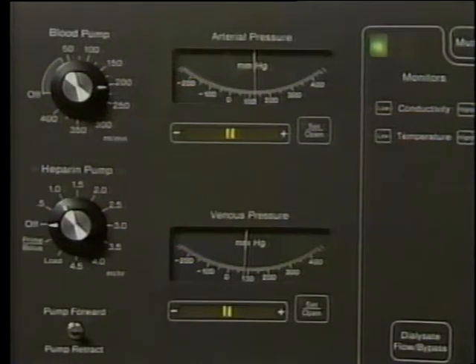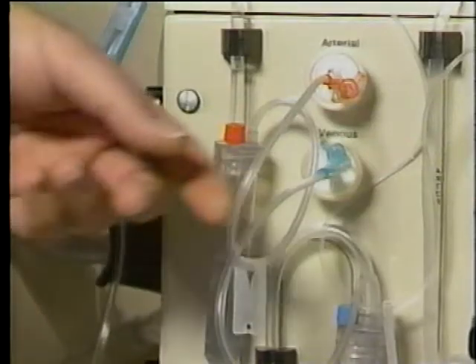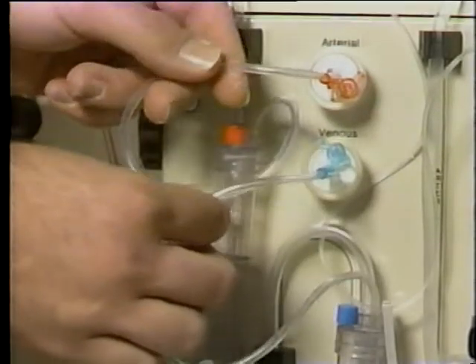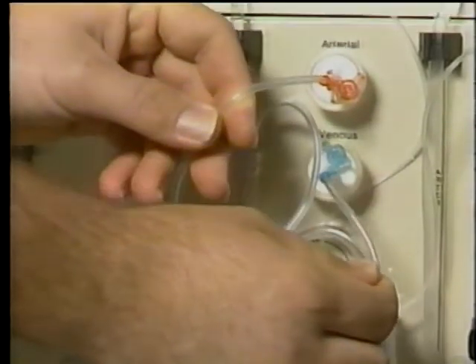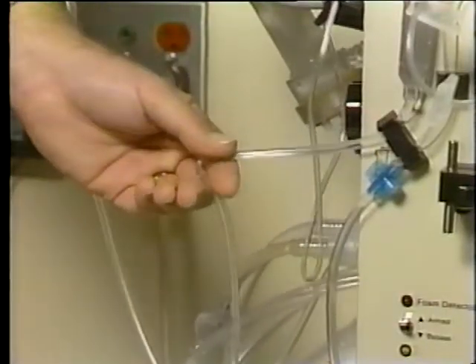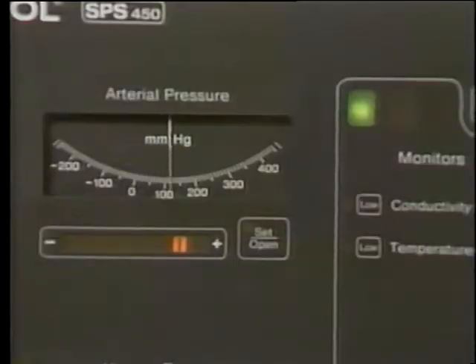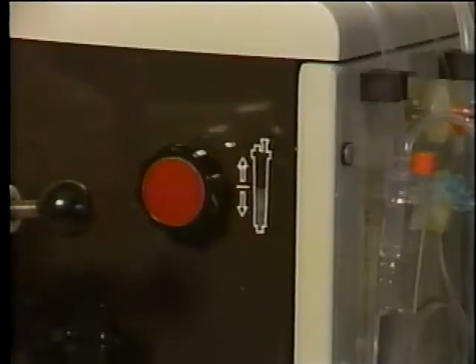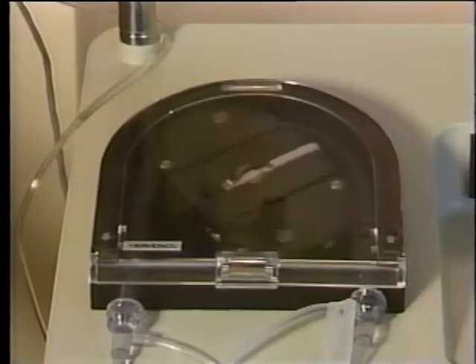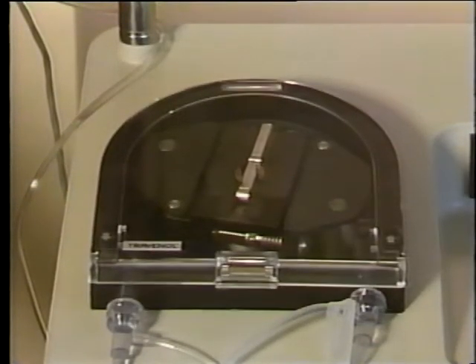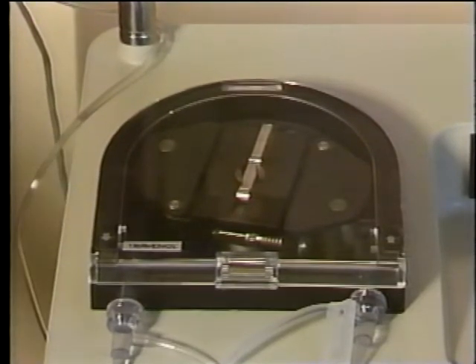It is possible for the patient to experience significant blood loss during treatment, so the limits for arterial and venous pressure should be set as soon as dialysis is started. Be sure that there is no fluid in the monitor lines, or the monitors will be disabled. The alarm should alert you immediately if an obstruction or separation in the blood circuit develops. To test the pressure alarms, override the monitor needle with a limit indicator. Verify both audible and visual alarms. Also verify that the blood pump stops.